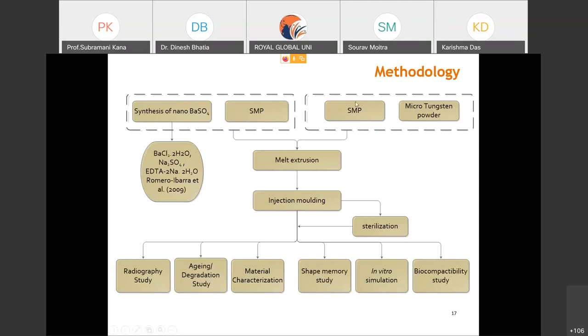When you use tungsten and polyurethane, whatever medical grade we have purchased, they are hydrophobic in nature. The glass transition temperature of this material depends on the moisture content of the polymer. The raw material has a transition temperature of 35, and after moisture is absorbed, this was not even reported. After we made the test samples, the characteristics were not up to the mark. We wondered what the probable reasons could be, and finally found that one of them could be moisture absorption.